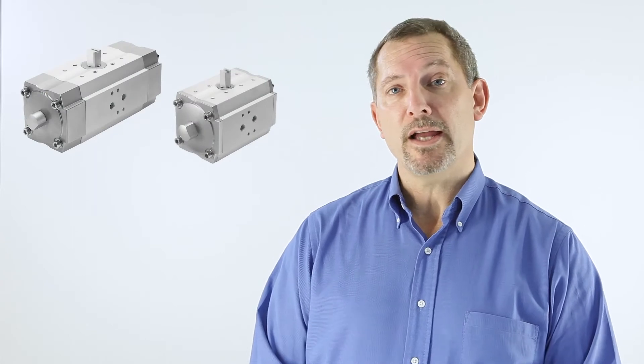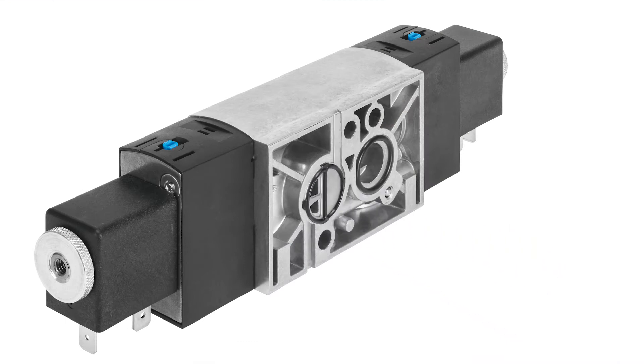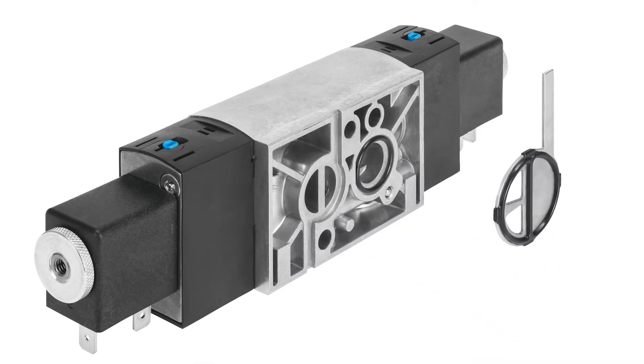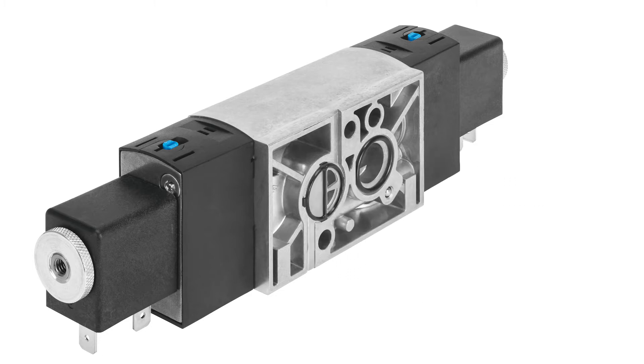Like every other solenoid valve, the VSNC consists of a basic valve and coil. But whether you are using a single or double acting actuator, we can offer you a solution with just one valve. By simply rotating the seal on the NAMUR interface, you can switch quickly between 3/2 and 5/2 valve functions, as and when you need.